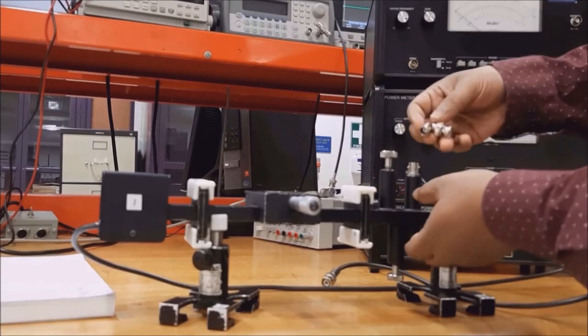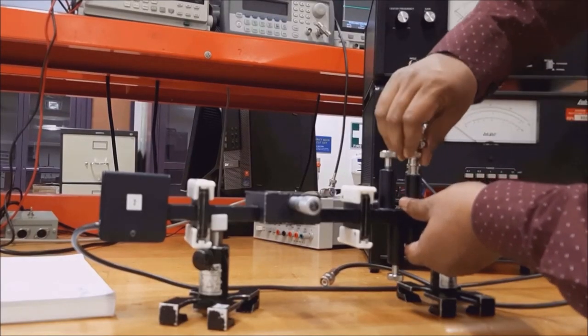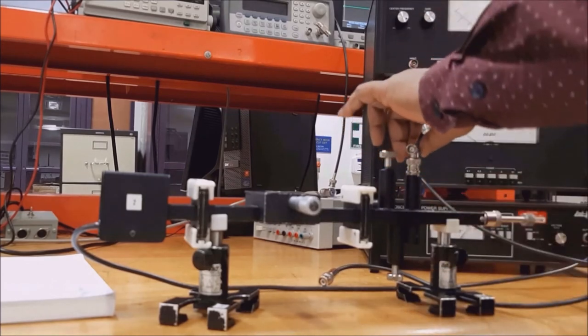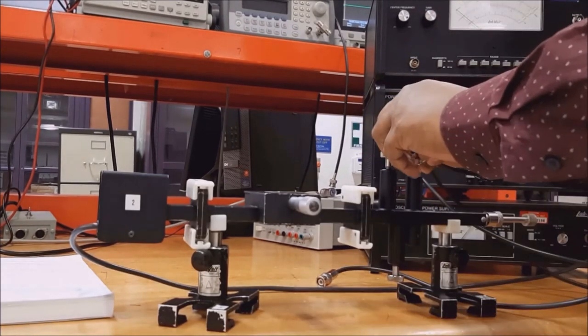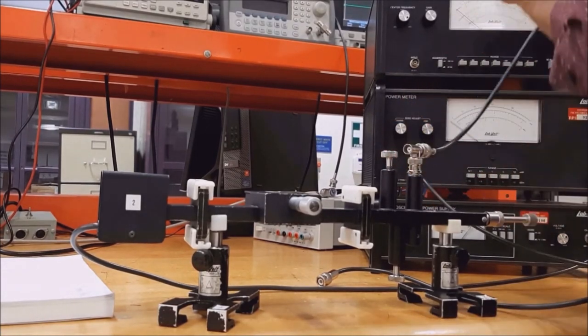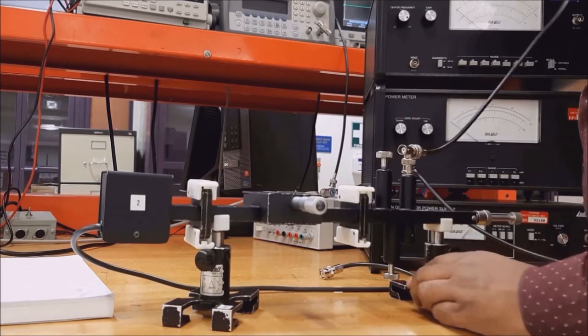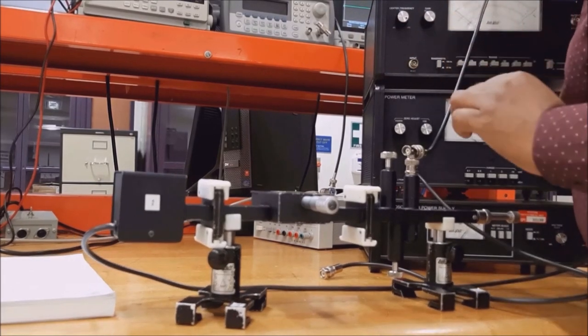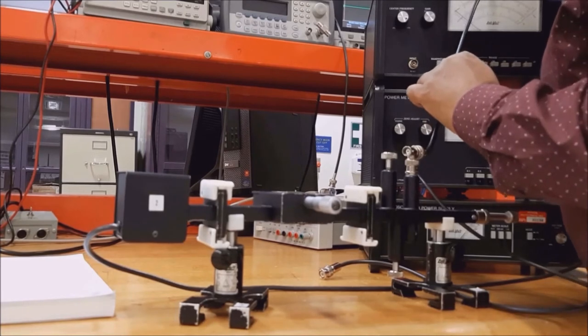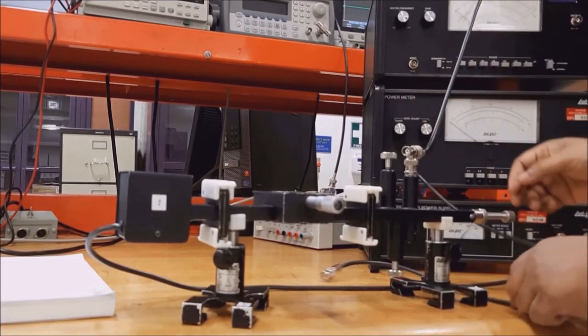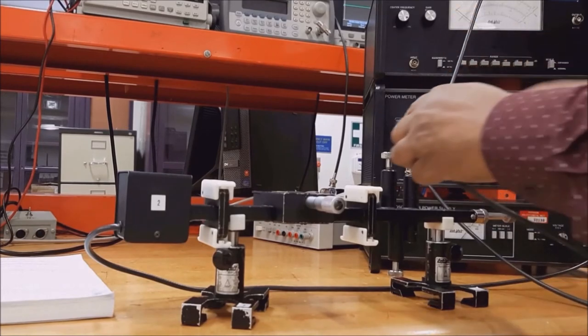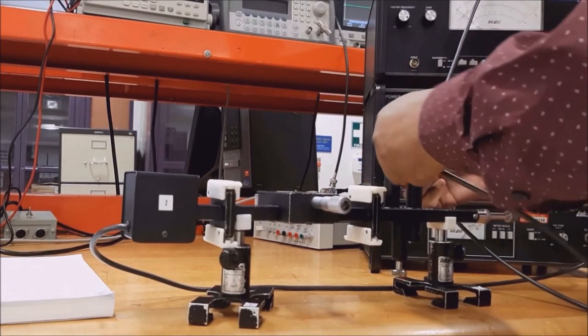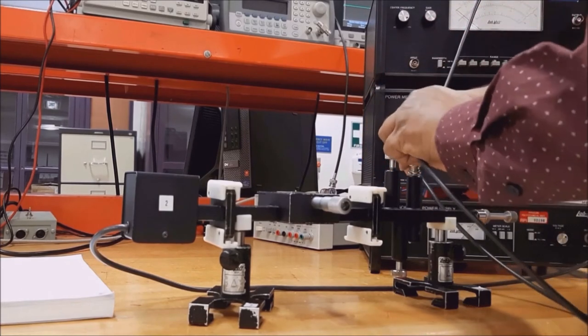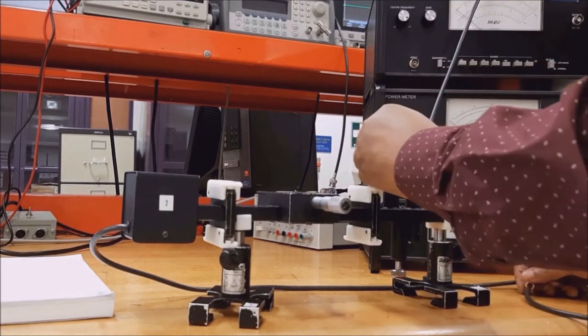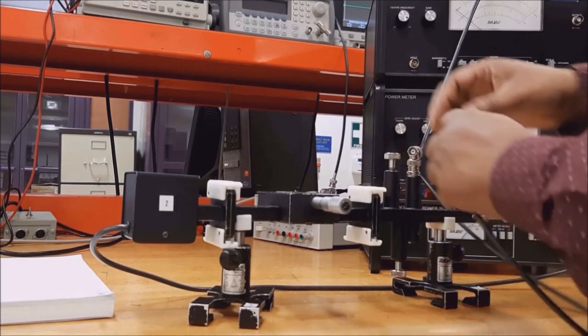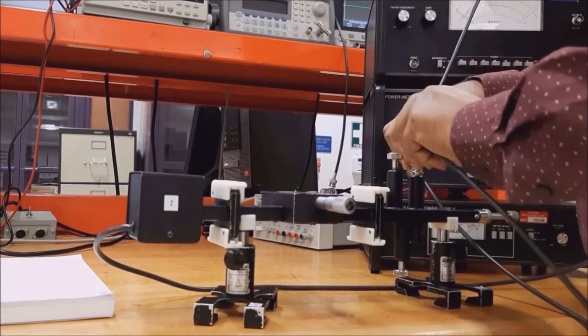Now we have to measure the power. So to measure the power we need power meter and oscilloscope. So I use a T connector. One will be connected with the power meter and another terminal will be connected to the oscilloscope. So I'm connecting oscilloscope with one port of the T connector and I am connecting power meter to the other terminal. So this cord is going to the input terminal of the power meter.